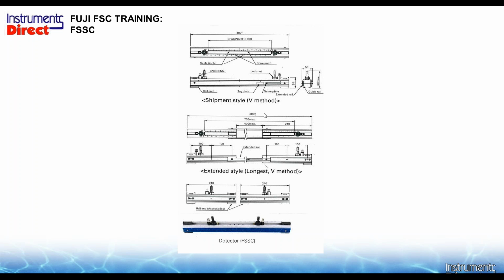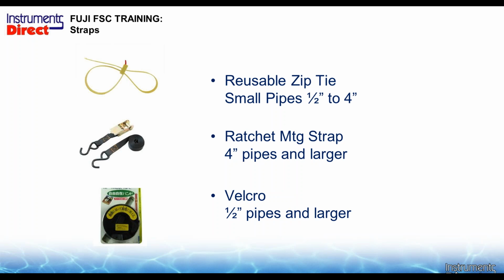The FSSC transducer, as you can see here, here it is standardly, but it has the ability to expand, so you can literally move some screws and it slides out and expands to a longer transducer rail. And in addition to that, you can pop off the 2 blue extensions, and then you can have 2 separate transducer rails. So if you needed to do that Z configuration on that large pipe size application, it's all in one transducer. So very user-friendly from the breakdown of the V and the Z configuration, and makes life a whole lot easier, one less thing to carry around.